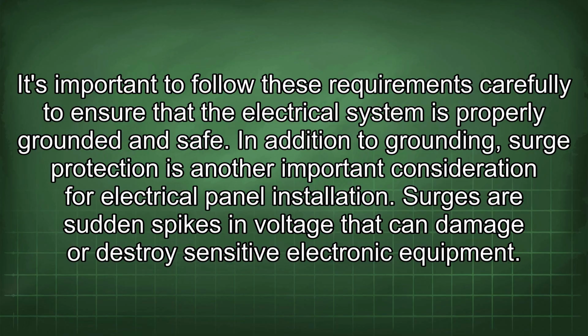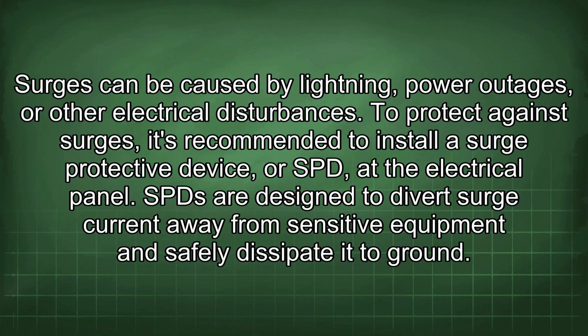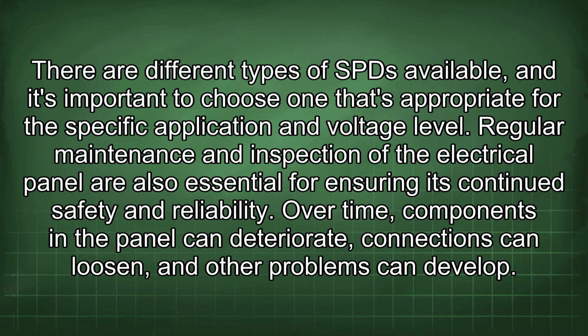In addition to grounding, surge protection is another important consideration for electrical panel installation. Surges are sudden spikes in voltage that can damage or destroy sensitive electronic equipment. Surges can be caused by lightning, power outages, or other electrical disturbances. To protect against surges, it's recommended to install a surge protective device, or SPD, at the electrical panel. SPDs are designed to divert surge current away from sensitive equipment and safely dissipate it to ground. There are different types of SPD available, and it's important to choose one that's appropriate for the specific application and voltage level.